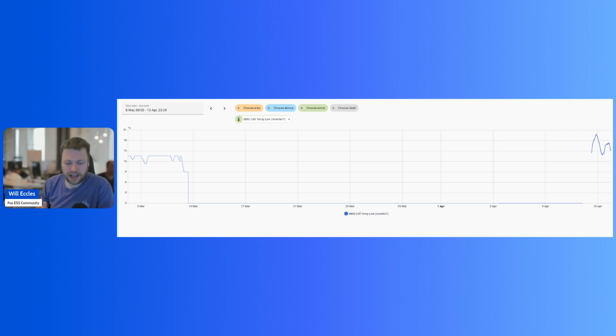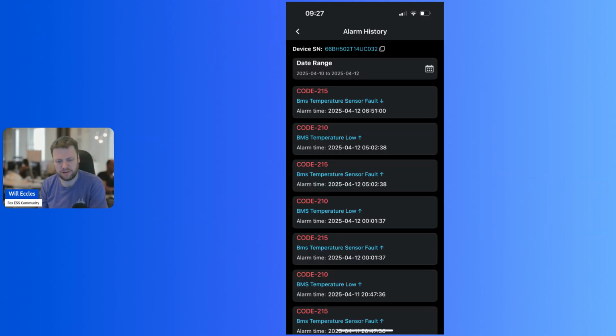I think the system knew something was going on. It's a shame I couldn't just tell it to ignore and bypass, because it knows there's a temperature sensor fault. It would be nice if it could tell me, as an installer, which battery pack or serial number is registering the fault. What it gave me was the serial of the BMS, calling it a BMS temperature fault, but it wasn't the BMS.